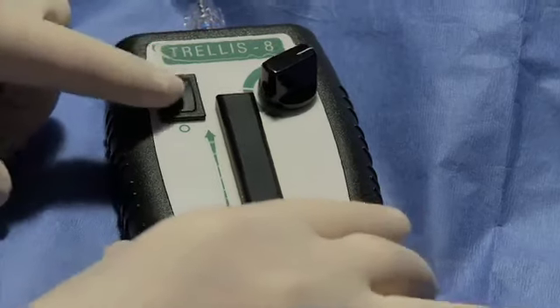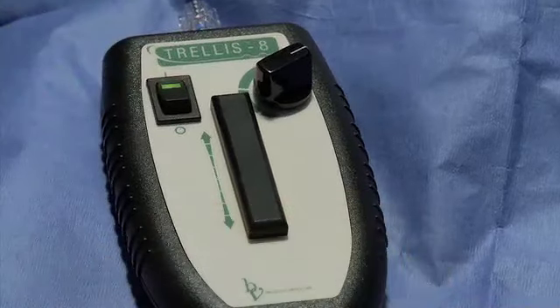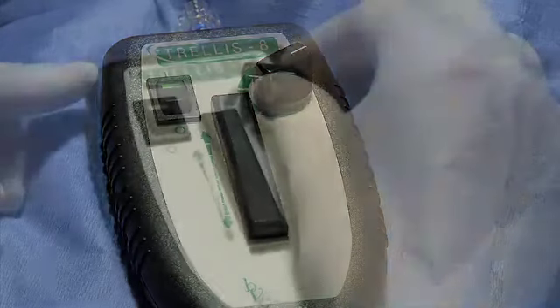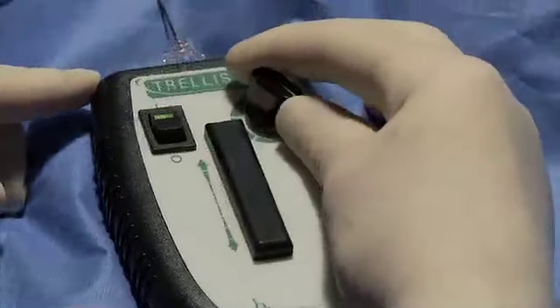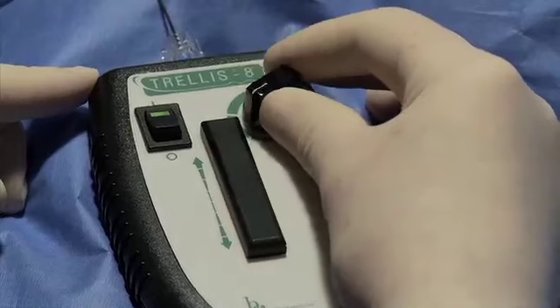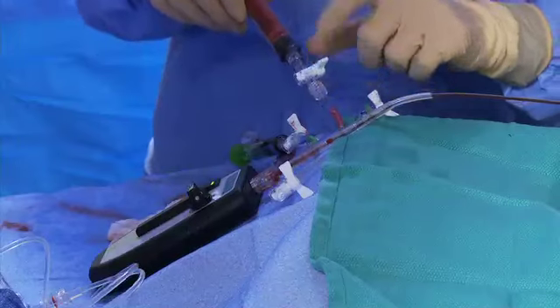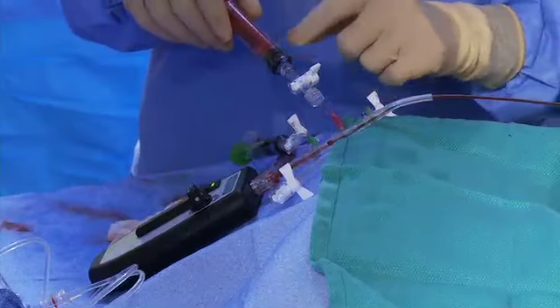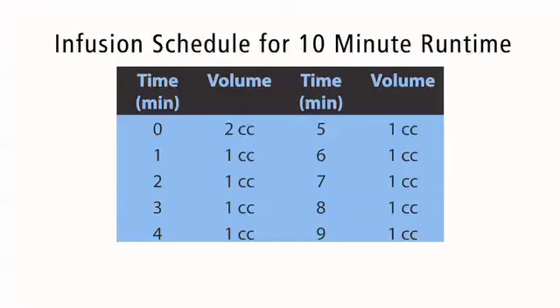Activate the on-off switch located on the ODU. Note the time at which oscillation has begun. Adjust the speed of the ODU per physician preference. Begin infusion by injecting the physician-specified fluid via the infusion port. Use the following infusion schedule as a guide for a 10-minute runtime.